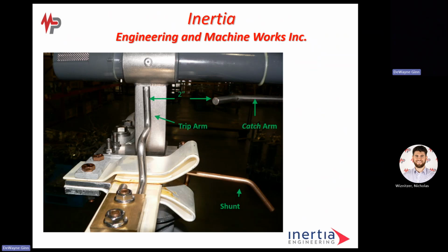So if you look at the jaw, which is where the blade is inserted, that's a reverse loop contact jaw. If you look at the way it's designed, it curls around. So when it's energized, it starts putting pressure onto the blade. If I had a surge in the power, it just clamps down tighter on the blade, so it does not try to expel the blade out of the jaw. That's a safety feature, if you want to call it that. It was designed by Westinghouse engineers back in the 1950s, when Westinghouse was the leader in the utility world. It allowed switches to go up to higher voltages, 115, 230, and above. It was a patented item for many years. We put this on all of our switches, whether it be 15, 25, 38, 46, 48, or 72 kV switches. All of our construction is the same, so we put it on all of them.